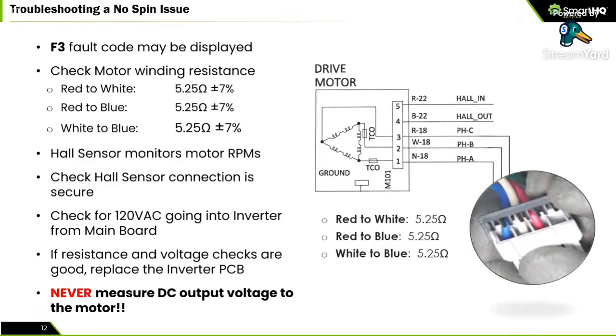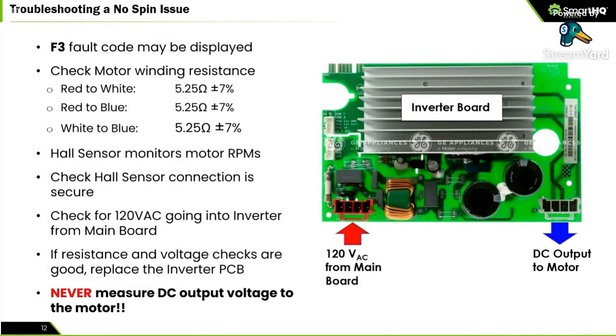Now we go into the inverter board. The inverter board looks exactly like the picture you see right there. That inverter board gets 120 volts AC from the main board, and it outputs a DC voltage to the motor. Now, you're not going to be able to check the DC voltage that goes to the motor, but you can check the 120 volts AC that goes into the inverter board from the main board. So check for that first, check the 120 AC, and again, refer to your schematic diagram to ensure which pins you're going across. It's probably just going to be two wires, so check across those two wires. Make sure that you are actively getting 120 volts AC from the main board. If you don't get 120 volts AC from the main, chances are the problem is not the inverter, it's the main control board, because that's the one that's supposed to supply the 120 volt AC power.